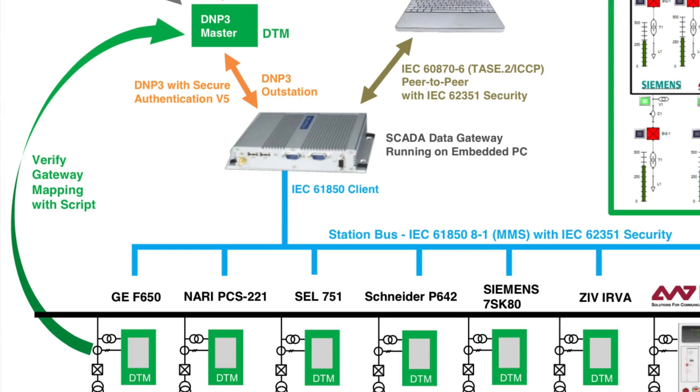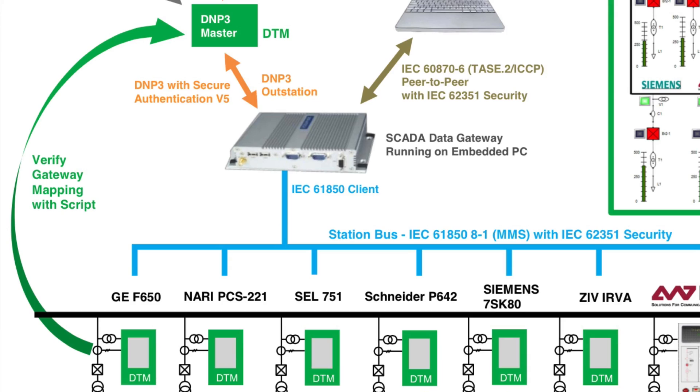A DTM script changes each mapped data point in a simulated IEC 61850 server and verifies that only the corresponding point defined in an Excel spreadsheet changes in the DNP3 master.